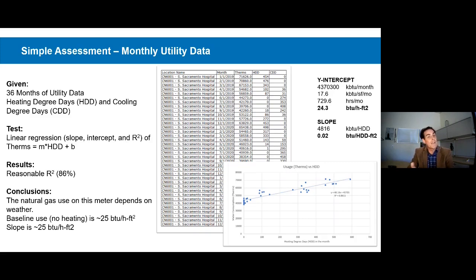The first time I saw that, my head exploded because it stands against everything I've ever learned as a mechanical engineer. But I will tell you, it's very common. In this example that I'm showing on the screen, there is a relationship. So we're looking at a linear regression of the relationship between heating degree days and monthly natural gas use. The relationship here is reasonably strong. We have an R-squared that's better than 80%, and we have a line that actually has a slope.